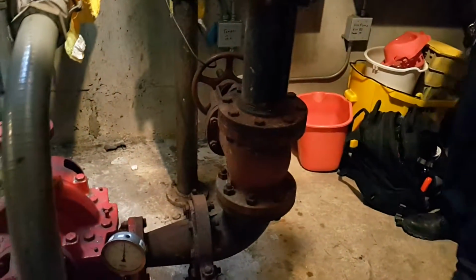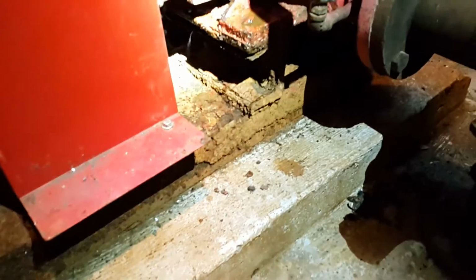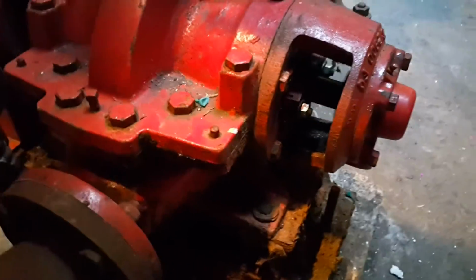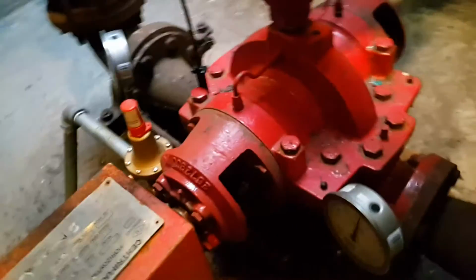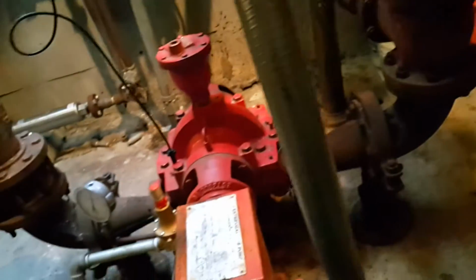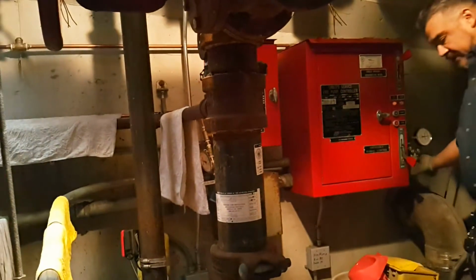You can monitor it. I'll adjust this packing down and drop a little bit less water right here inside. What the manufacturer recommends is 1 to 2 drips per second. So this side is pretty good, right? Yeah, this side is good. Yeah, that's perfect right there. And then same thing with this, we'll take this cap off here.